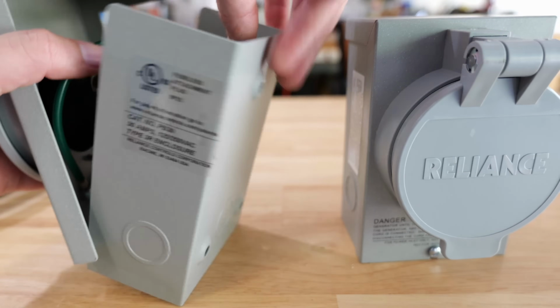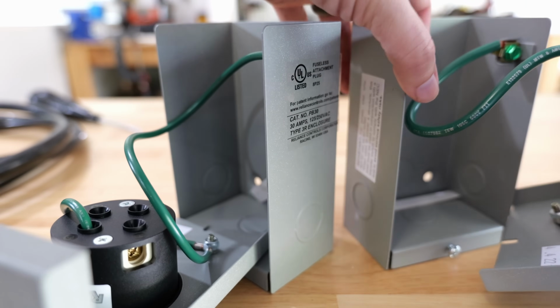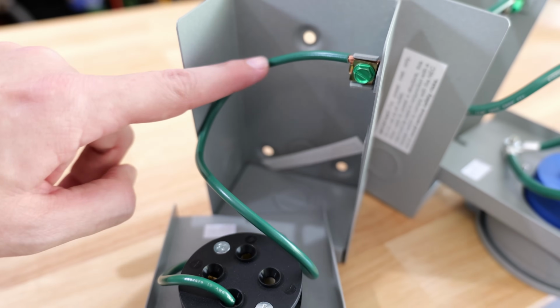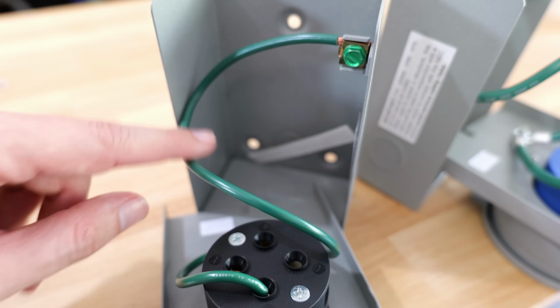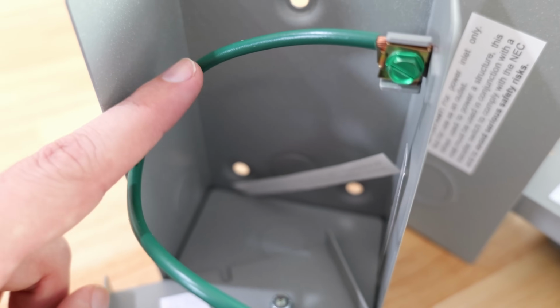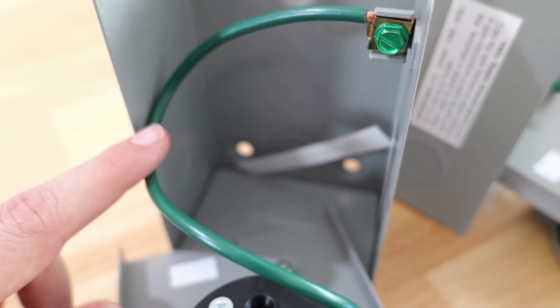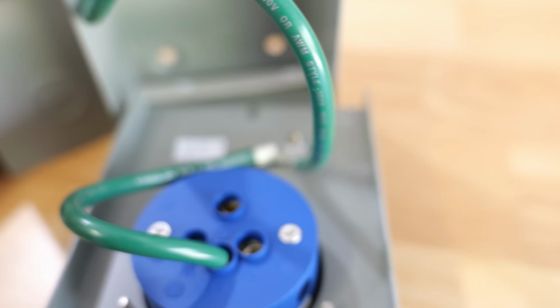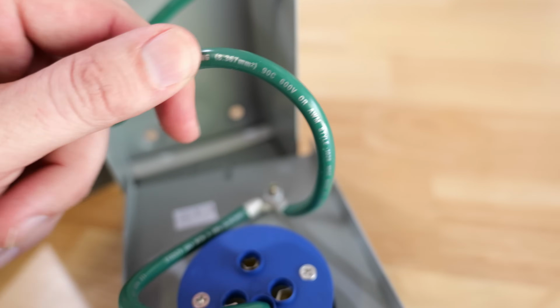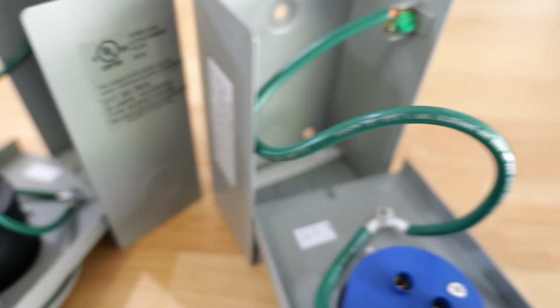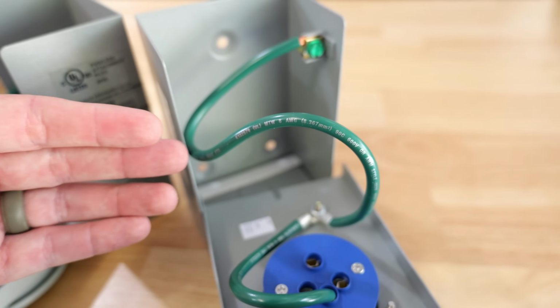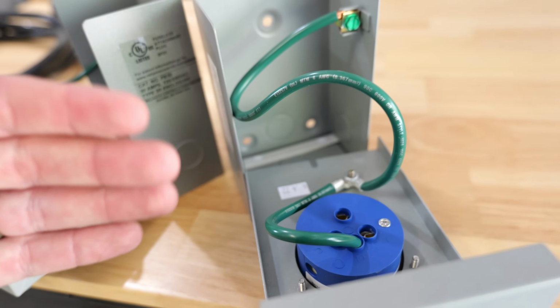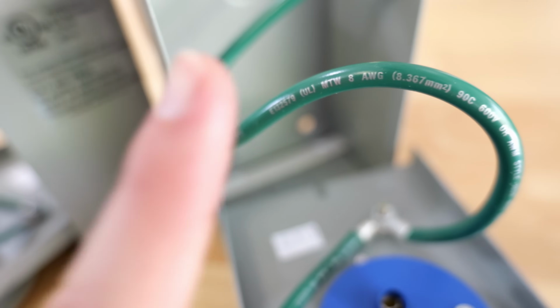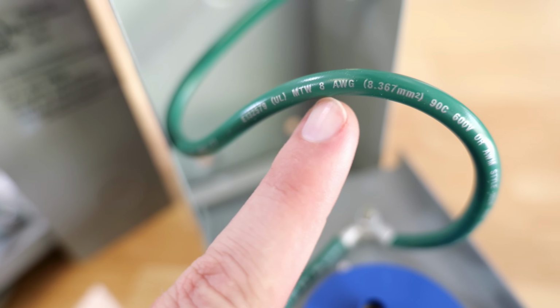But now let's look at the insides of these power inlet boxes. So again, we've got our 30 amp power inlet box over here, and you look at the size of this green wire. This wire size is number 10, or 10 gauge wire, which is suitable for up to 30 amps. If we come over here to the 50 amp power inlet box, look at how much wider and how much thicker this wire is. There is a huge noticeable difference between the two grounding wires. And that's going to be reflective of the other wires that would be installed with this as well, with the neutral and the hots. Now the grounding wire size of this 50 amp power inlet box is number 8.